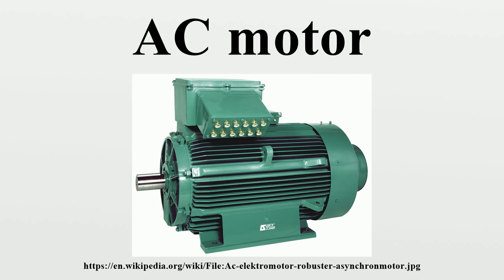A typical two-phase AC servo motor has a squirrel cage rotor and a field consisting of two windings: a constant voltage main winding, and a control voltage winding in quadrature with the main winding so as to produce a rotating magnetic field. Reversing phase makes the motor reverse.